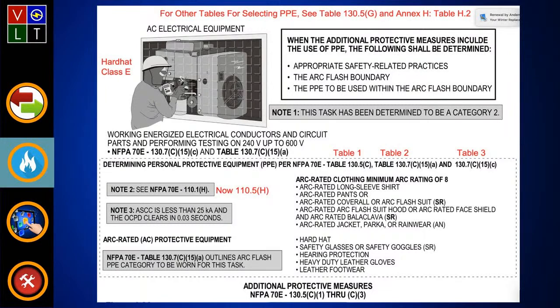He did it. Now, note 3: our available short circuit current is less than 25 kA, and our circuit breaker will open up in a half cycle. Now, if you take the cycles and multiply by 0.0167, that gives you your seconds. Take the seconds and divide by 0.0167, and that'll give you your cycles. Nice. So if we fall within note 3, then we go down and select our equipment that we're going to wear for this task, and there it's listed, and that would be a category 2. Excuse me, it would be a minimum arc rating of 8 cal/cm², and that's the equipment you need for a category 2, and then the clothing, and then the hard hat and the equipment that you wear would be listed below that. So you need safety glasses or safety goggles. And by the way, what would make you use safety glasses or safety goggles?